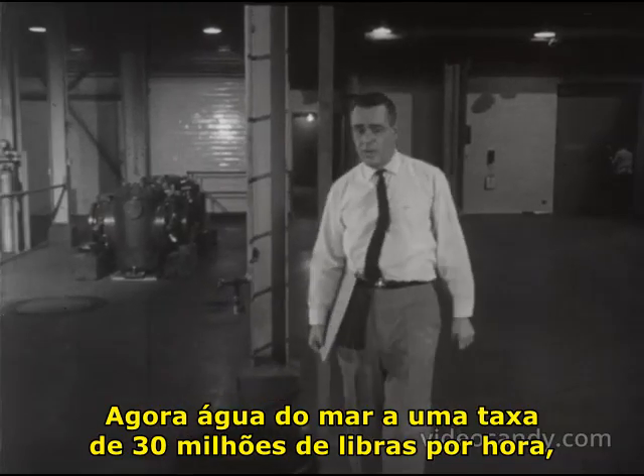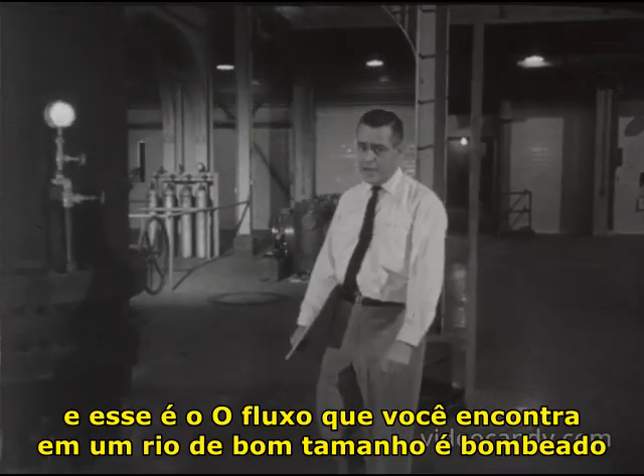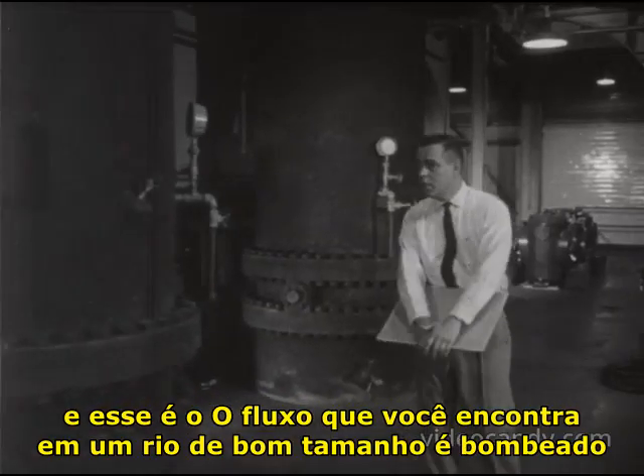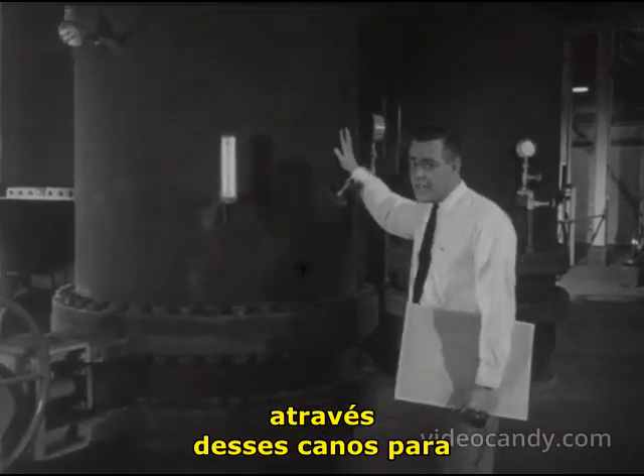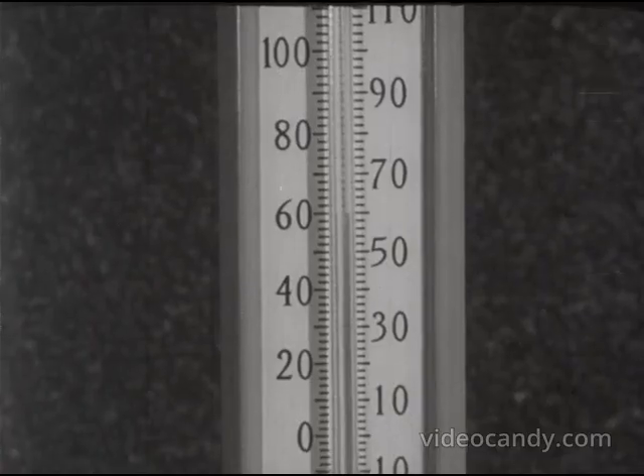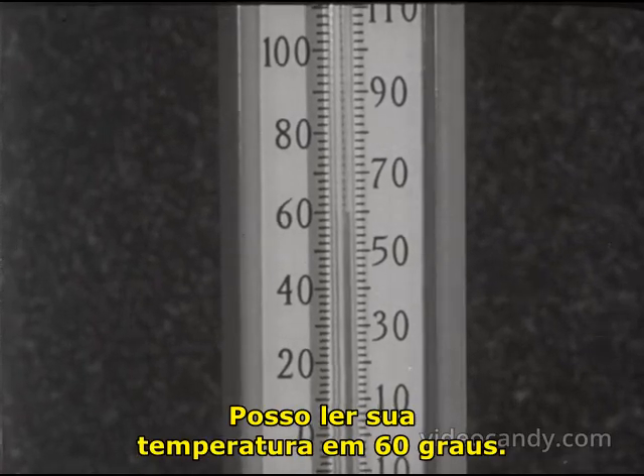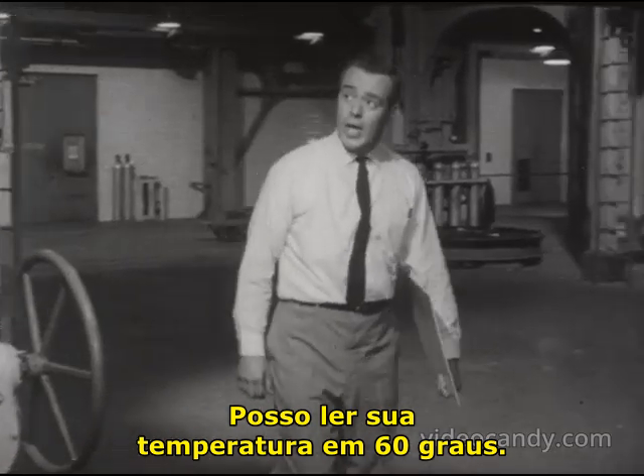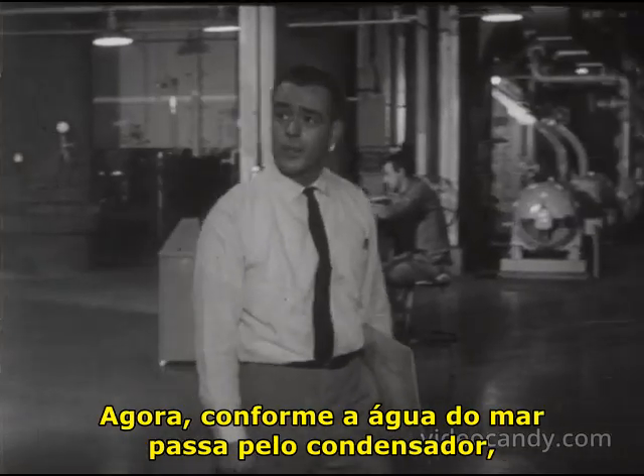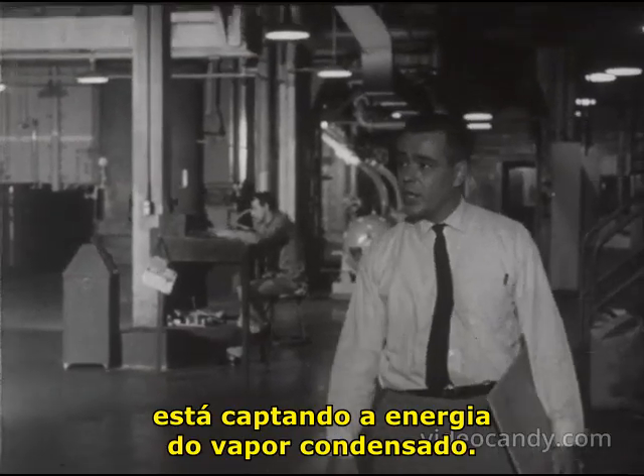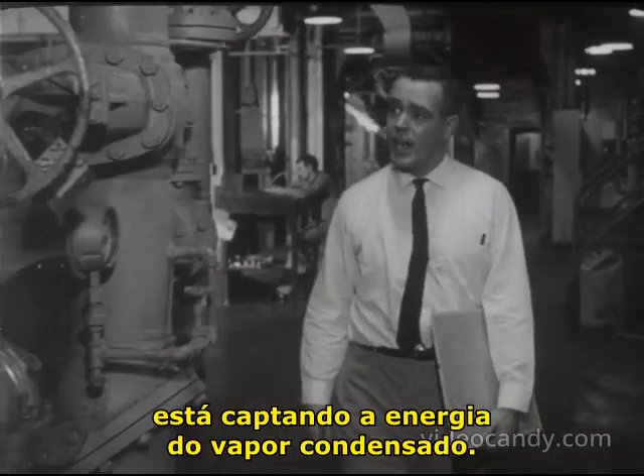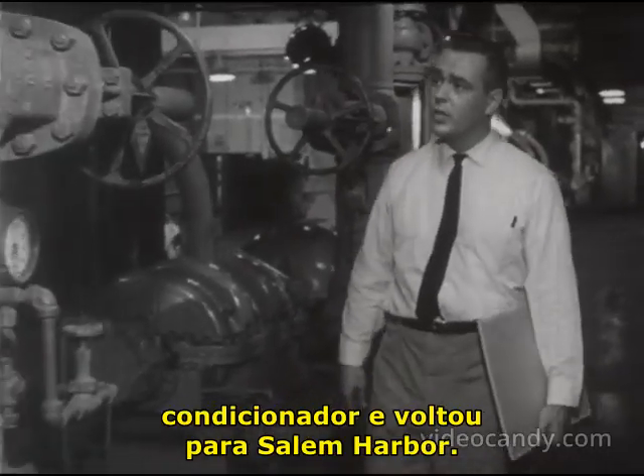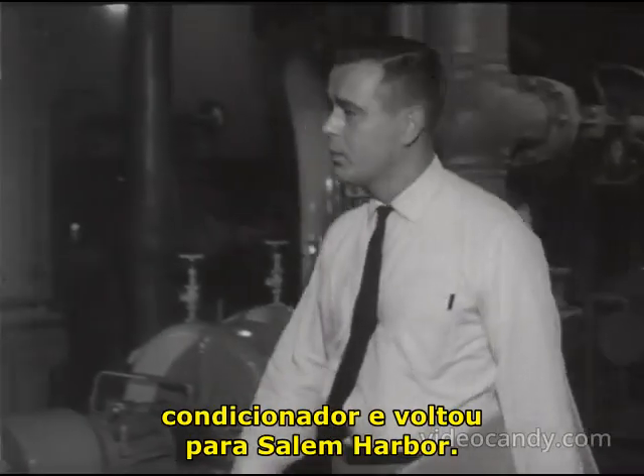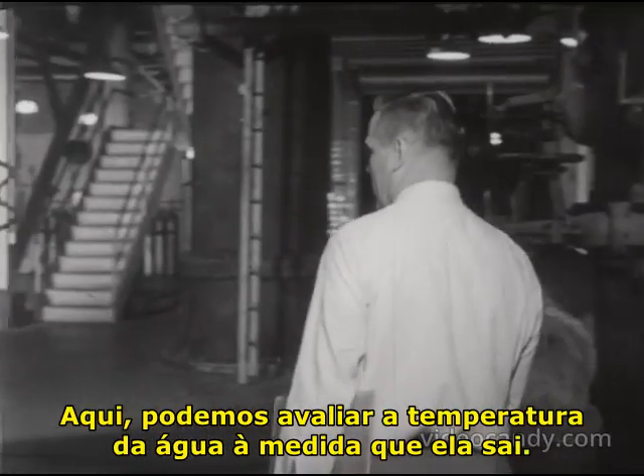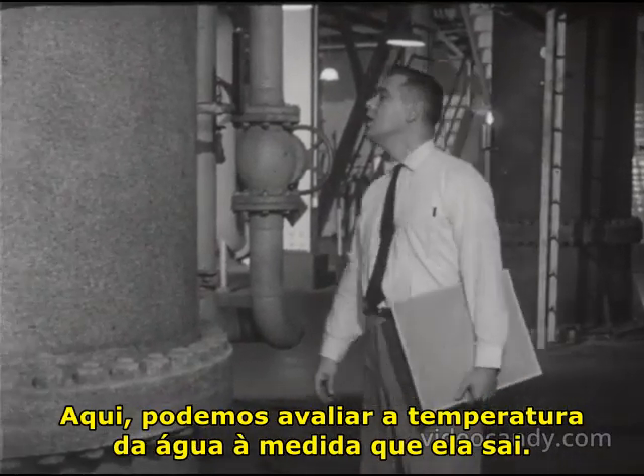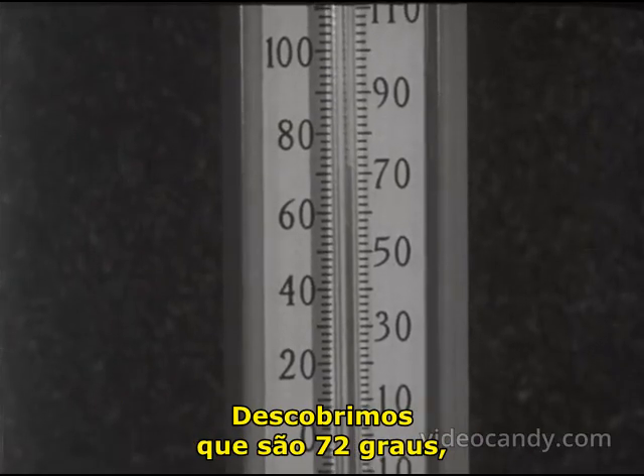Now seawater at the rate of 30 million pounds per hour, and that's the flow you'd find in a good-sized river, is pumped through these pipes into the condenser. Over here, I can read its temperature at 60 degrees. Now, as the seawater goes through the condenser, it's picking up energy from the condensing steam. And then finally flows out the back end of the condenser and returns to Salem Harbor. Over here, we can read the temperature of the water as it leaves, and we find that it's 72 degrees.